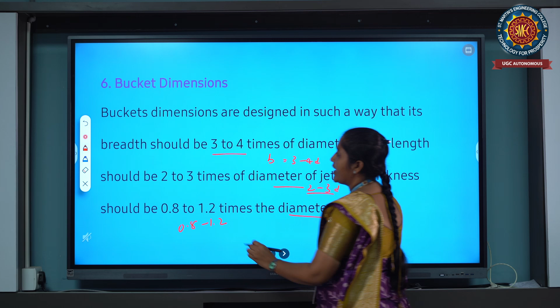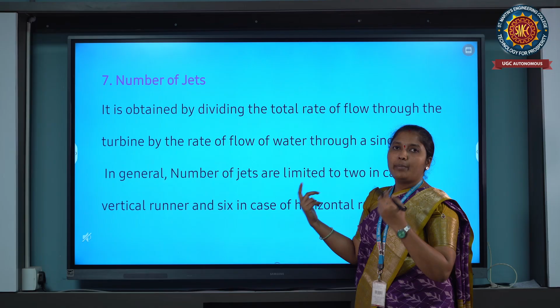And the next one is the number of jets. We can calculate the number of jets depending on how many are rotating on the runner. And the next is the number of buckets. The number of buckets should be equal to 15 plus D by 2d. So according to that we can calculate it. Here D is the pitch dia, small d is the dia of the jet, and m is the jet ratio. We already learned that the jet ratio m is equal to capital D by small d.